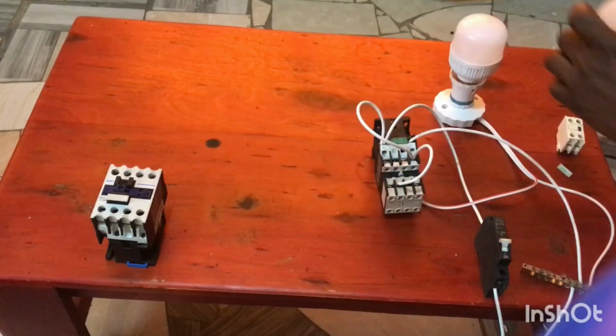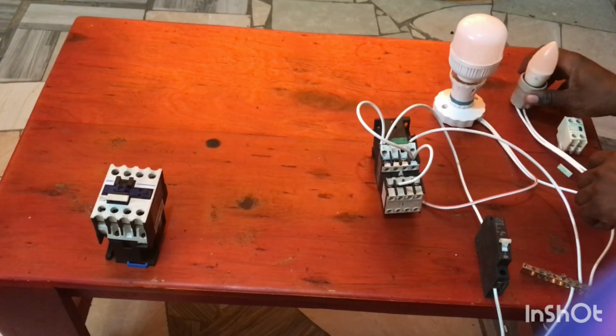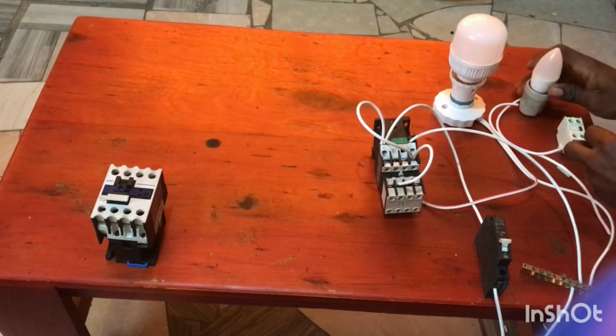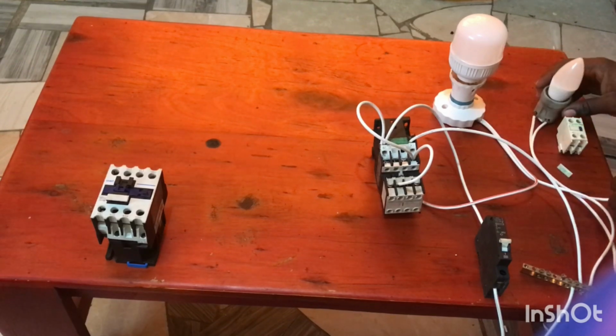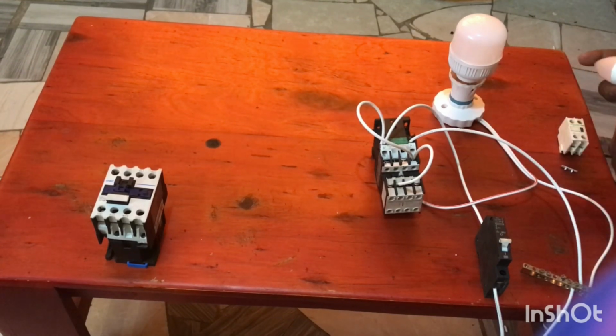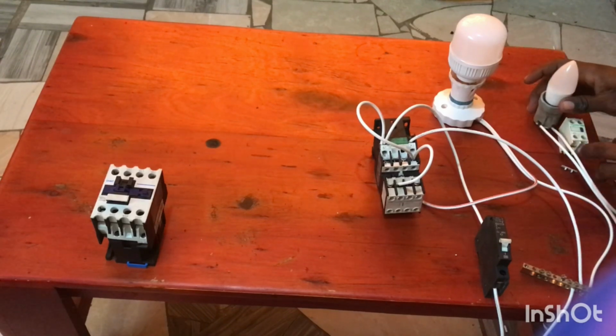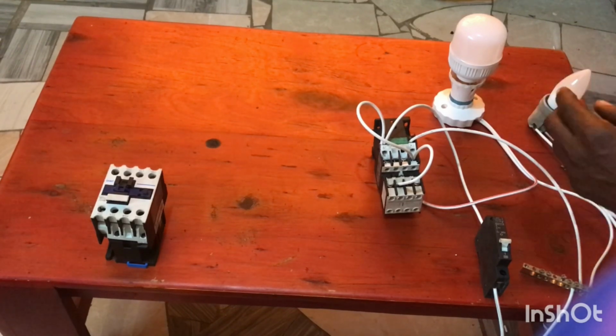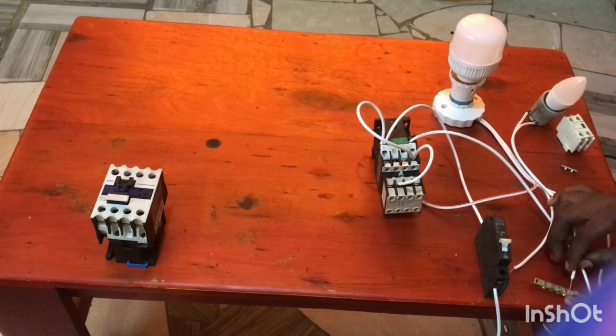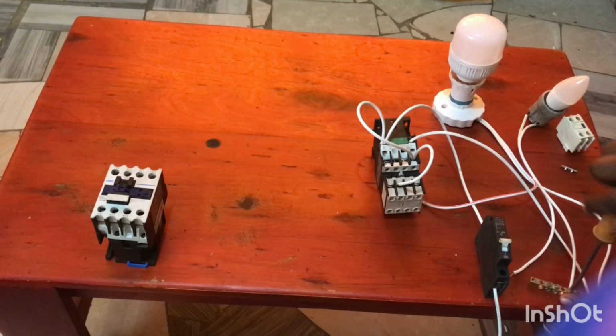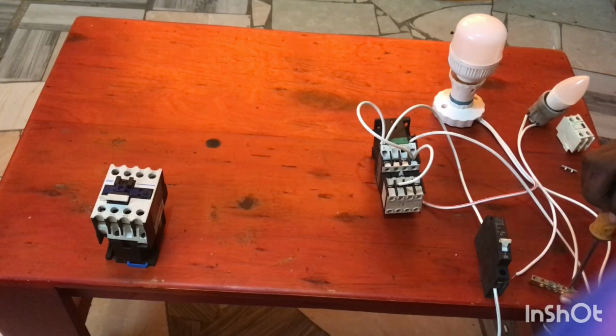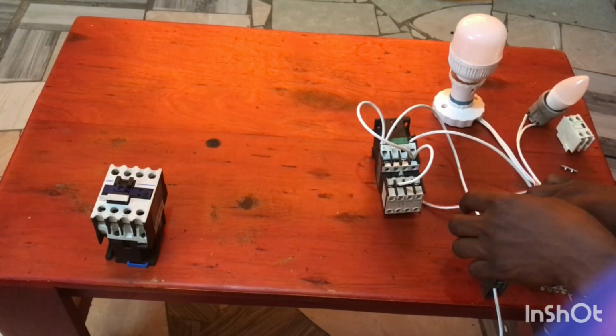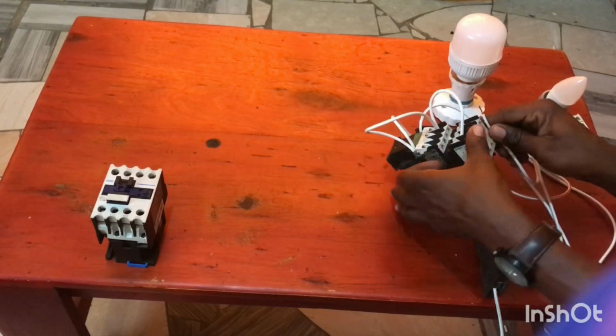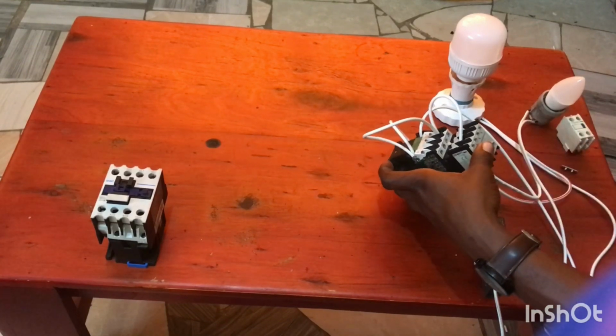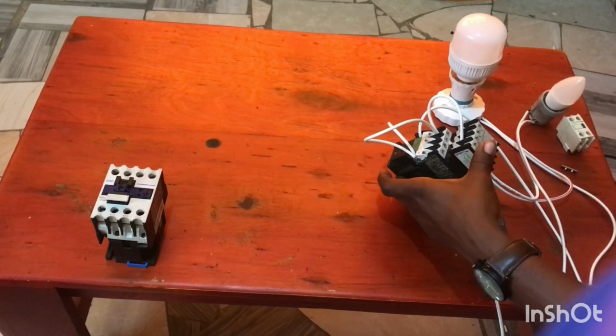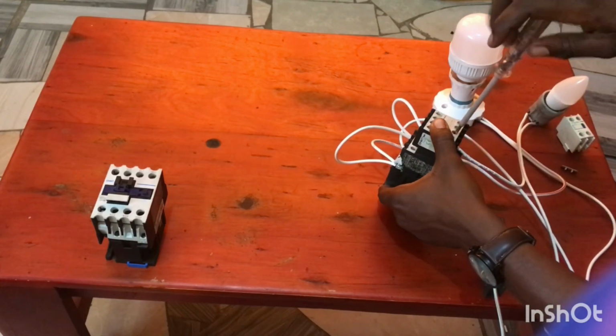Remember, there is no power coming from the auxiliary, so we have to take power from either A1 or where it is, then put it to the inlet of the auxiliary normally closed. We put our ground to the neutral bar for light number 2. Then we put our line cable from the outlet of the normally closed contact.